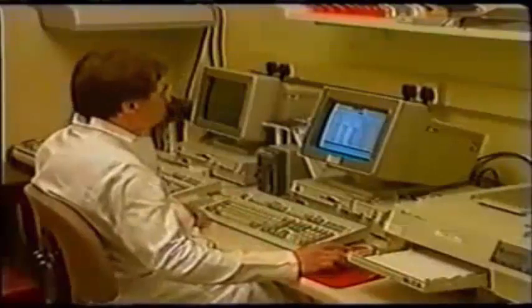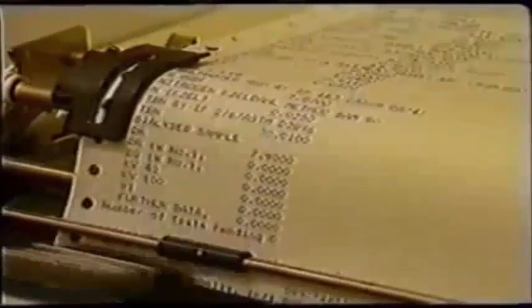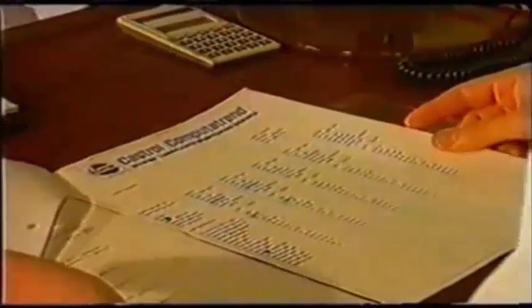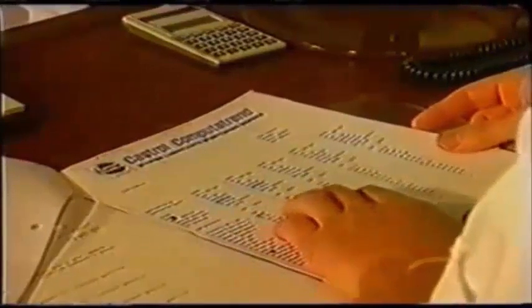In the laboratory, the lubricants will be examined for the presence of combustion contaminants, as well as for metal debris against established control values. Increasing trends and their combinations will allow the required remedial measures to be formulated. Modern lubricating oils, when carefully monitored and maintained in good condition by the engineer, can have an almost infinite life. Even if this optimum is not always achieved, extended oil change intervals will reduce used oil disposal problems with significant cost and environmental benefits.